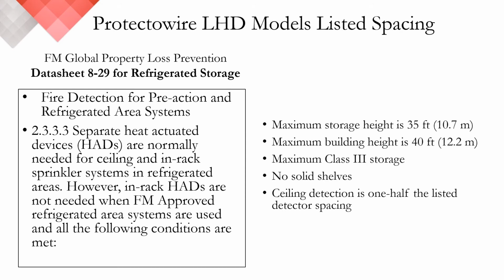Now I want to discuss how and when to install in-rack HADs or heat actuated devices. Typically, a separate detector, such as Protectowire, is required by FM for use with both the ceiling as well as in-rack sprinklers. There are certain circumstances, however, where ceiling detection only is acceptable. Section 2.3.3.3 of datasheet 8-29 further defines these conditions. Separate heat detection is not necessary when the facility has an FM-approved refrigerated area system and the maximum storage height is 35 feet, just under 11 meters, and the maximum building height is 40 feet, or just over 12 meters.